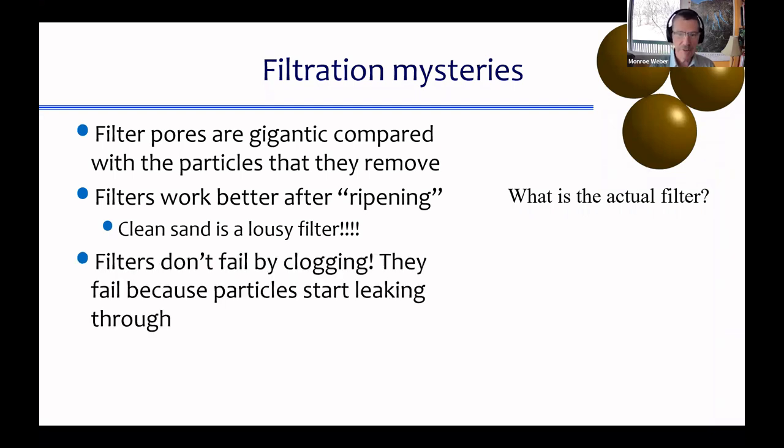Another mystery, filters don't fail by clogging. They fail because particles start leaking through. So it's not because you can't push the water through anymore that they fail. They fail because particles start leaking through. So particles start coming out the bottom of the filter. And so I'm beginning to lead the witness. I'm beginning to lead you now.